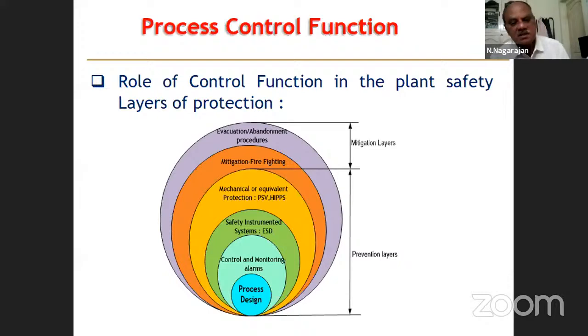HIPS is a preventive measure. When the process is designed for a certain operating pressure, if the incoming pressure from the outside source, meaning an external source, crosses the limits, then the HIPS system will close the inlet to the plant itself. It will stop the flow of fluids from the source to the plant. That is called HIPS.